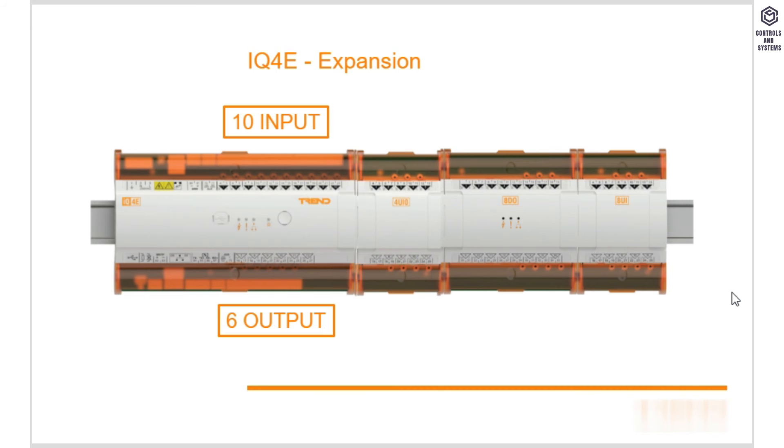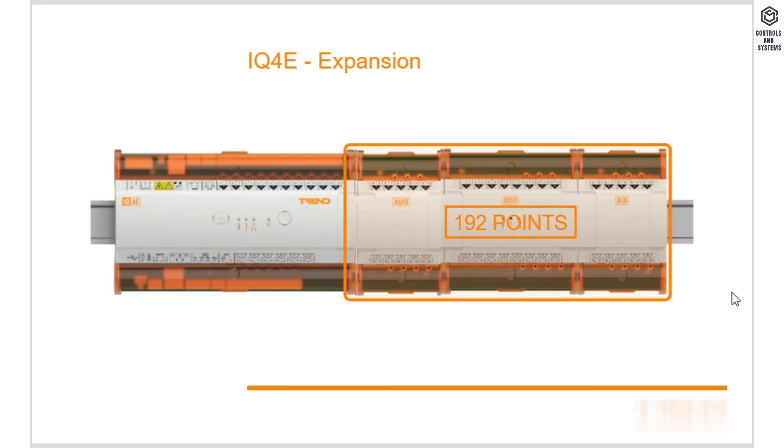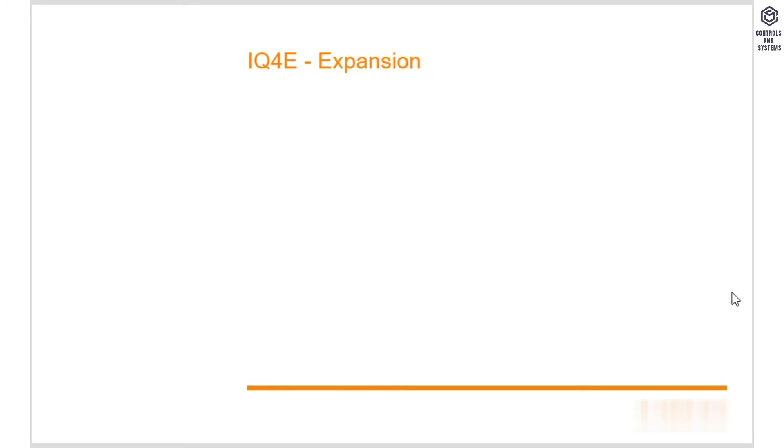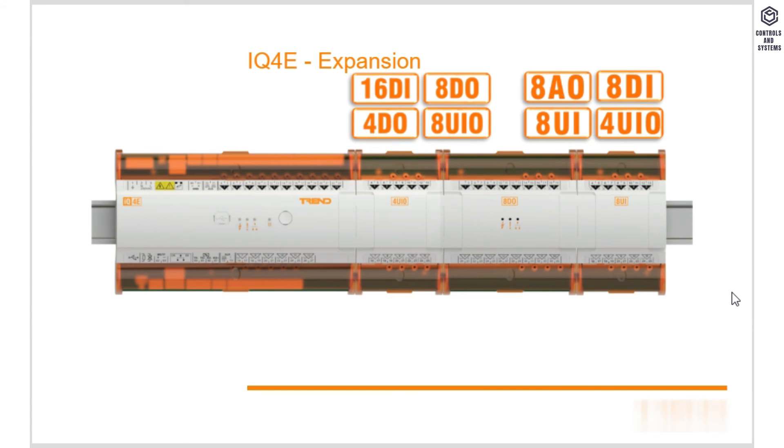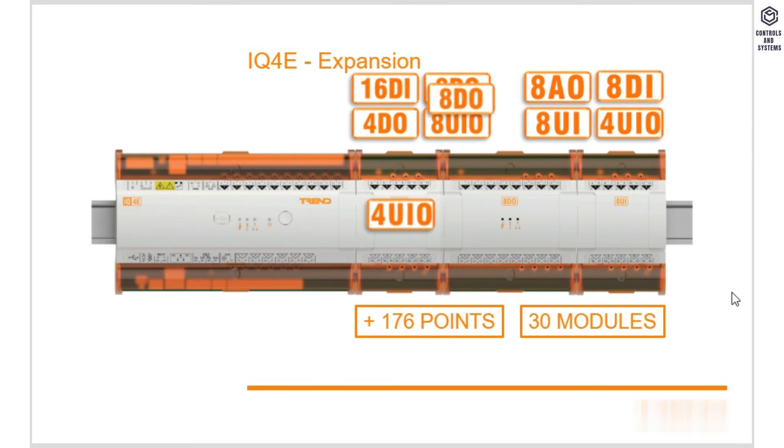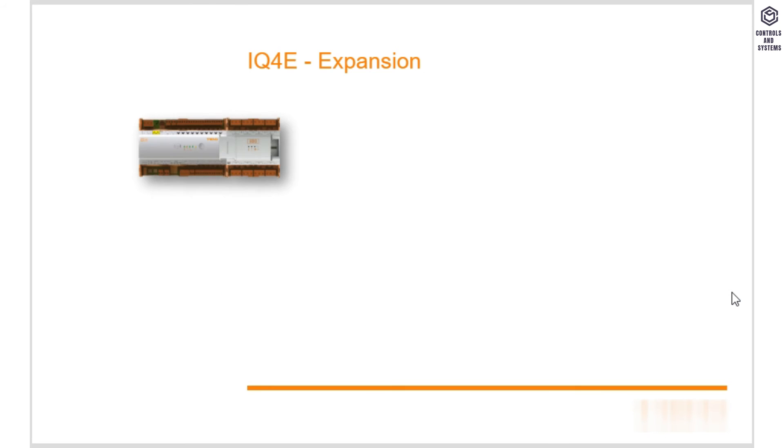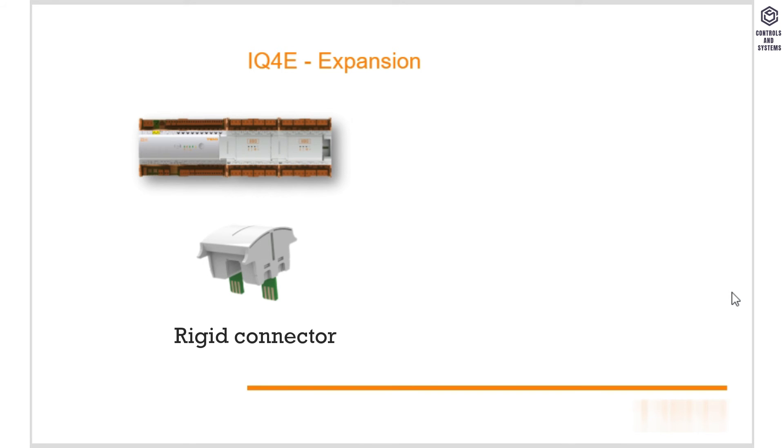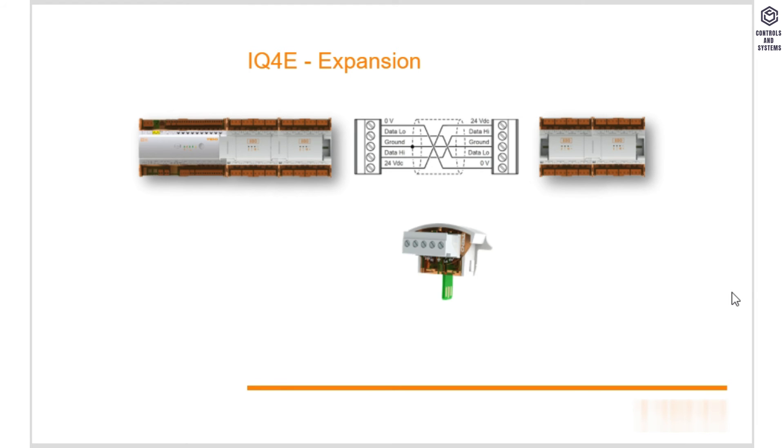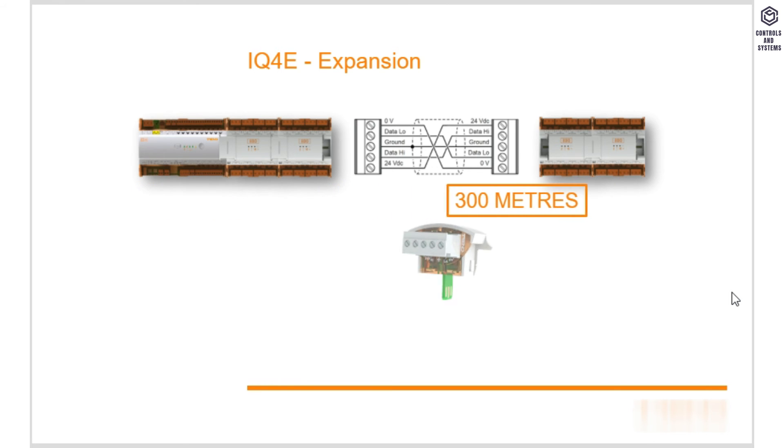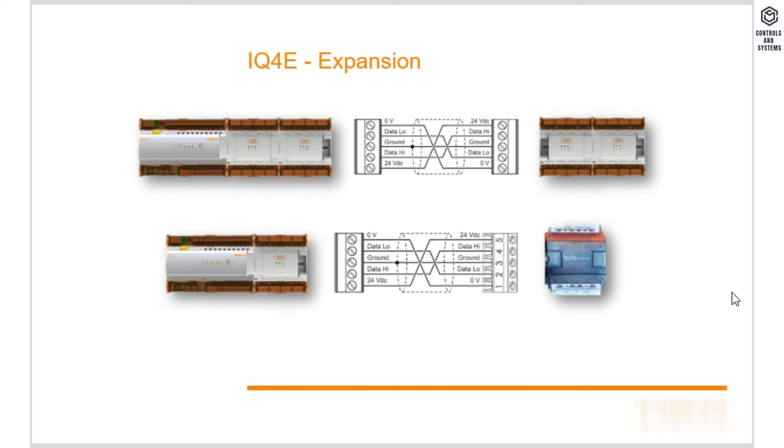But the more effective solution is one controller which can cope with all the inputs and outputs the area has. The IQ4E can be expanded from its standard 10 points in and 6 out, going all the way up to 192 points using expansion modules. There are few locations it cannot be suited for. The expansion modules can be selected as appropriate. It is important to note that the additional 176 points can be split over a maximum of 30 expansion modules of any IQ4 type. You can use either a rigid connector to join the controller to the expansion modules, or if you require additional flexibility within your plant area, you can use a wired assembly between modules. This gives up to 300 meters range between the main controller and the last item in the cable run. If you have a site with existing IQ3 expansion modules, these can be used with an IQ4E controller or mixed with IQ4 expansion modules.